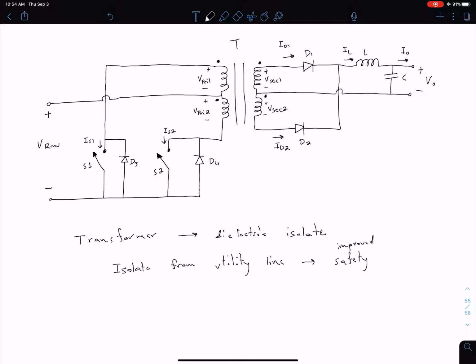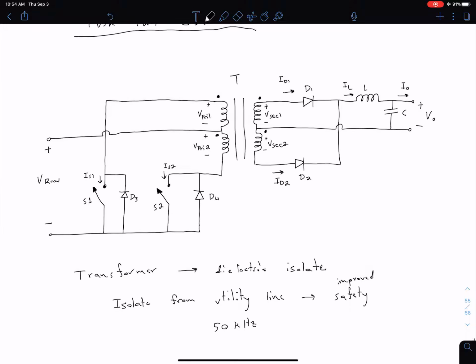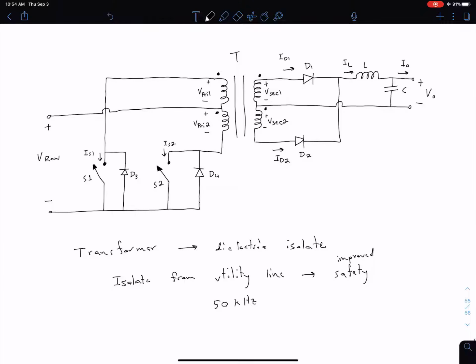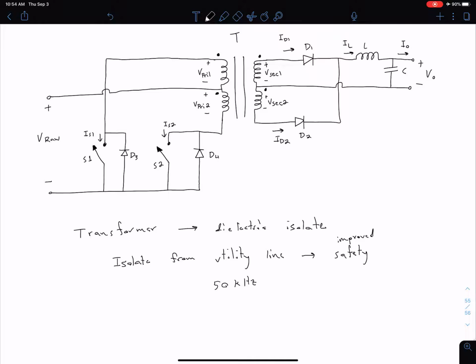But also we can have switching speeds operating at around 50 kHz instead of our 60 or 50 Hertz AC signal. So if we have a DC input on the left at 50 kHz, and we'll talk about how we get that using these two switches - if we have a high frequency signal and we're using a transformer to send that across to our secondary side, compared to our 50 or 60 Hertz utility lines, that means we need smaller cores and smaller windings for our transformer. Ultimately that translates to being cheaper and taking up less physical space.